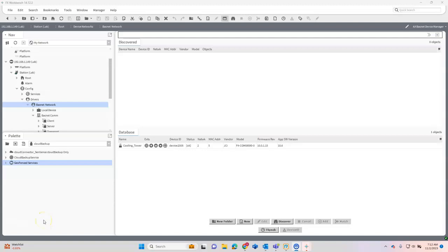Today, let's talk about what happens if you have a MAP gateway where you log into it and it immediately just starts flashing the fault light. So that's a known issue, and that just means it's lost its time sync. So here's how you fix it.